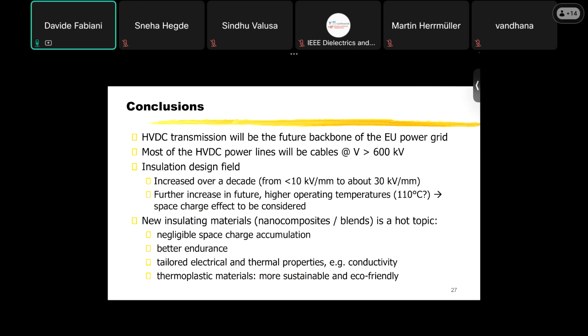To conclude, HVDC transmission systems will be the backbone of the future power grid, at least in Europe, but also worldwide - the use of HVDC systems is growing. Most of these HVDC power lines will be made with insulated cables, and voltages are now increasing, exceeding 600 kilovolts. So the insulation design field should increase further. It was less than 10 kilovolts per millimeter some years ago, and now cable companies want to exceed 30 kilovolts per millimeter. There will also be further increase in operating temperature - cable companies want to exceed 90 degrees, perhaps go to 110. And of course, space charge could be a problem in that case.